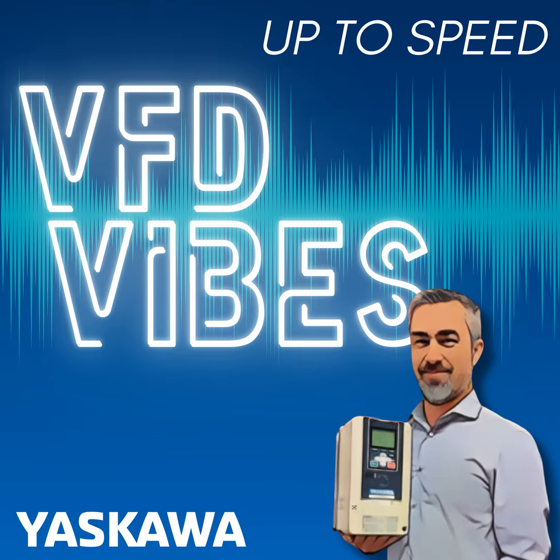Excellent. Now, let's say we're telling the drive to run, or at least we think we are. What are some things we should look at or do if our drive isn't running or operating the way we expect? Good question. And during my time in tech support, this is probably what we dealt with half the time, a motor not starting on a VFD. And oftentimes, the service technician would call in and say, I installed this drive. It's not starting the motor. I think I need a new drive. And I'd say, okay, hold on. Let's step back. I'd love to sell you one, but there's probably something else going on.